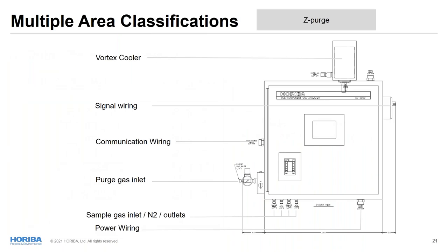All right, let's take a look at the outline of the VA-5000 wall mount here. The drawing on this page is the VA-5000 wall mount Z-purge unit. You can see that the vortex cooler and the signal wiring access are on the right side, and the communication wiring, which is the TCP/IP Modbus communication wiring, comes through the left side. The purge gas inlet is on the left. Here you can see the sample inlet, N2 carrier gas inlet, and then the gas outlet. Power wiring comes from the bottom. That's how the VA-5000 is designed.